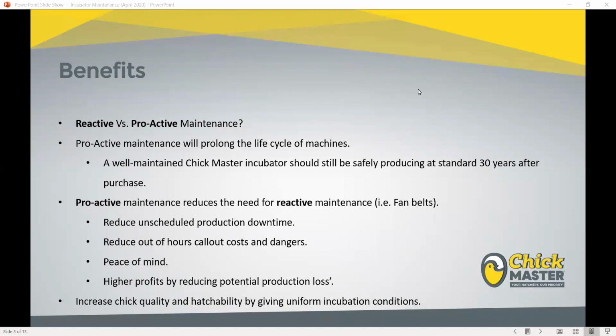Now, proactive maintenance will reduce the need for reactive maintenance in your machine. The obvious example to that is fan belts. Everybody that runs our incubators, and anybody that runs a system that has fans and belts in their system, knows that belts largely won't survive a 2-year period. They'll run quite happily for 12 months, and then in that 12 to 24 month period, you'll see an uptake in the number of failures that you're having on that hardware.